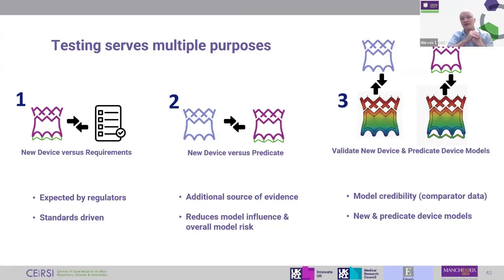So in terms of the in-silico strategy, which is the whole point of this talk, that testing, and this is important, could also act as an alternative source of evidence that is not modeling. And the modelers will know that if you have an alternative source of evidence that's not modeling, that reduces the overall model influence, which reduces the overall model risk. And the validation that we do of the model is commensurate with the model risk, so that will have implications for how well the model needs to be validated.